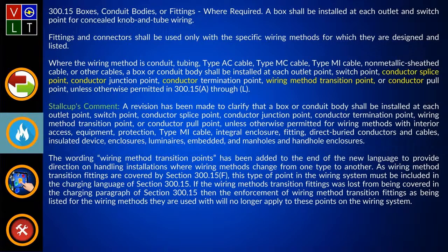Or conductor pull point, unless otherwise permitted for wiring methods with interior access equipment protection. That right there, the main point in all of that, in my opinion, is the wiring method transition point. That's telling you, where you're looking at these wiring methods and figuring out where you need to install a box or conduit body, this is where you're going to do it, at all these locations.